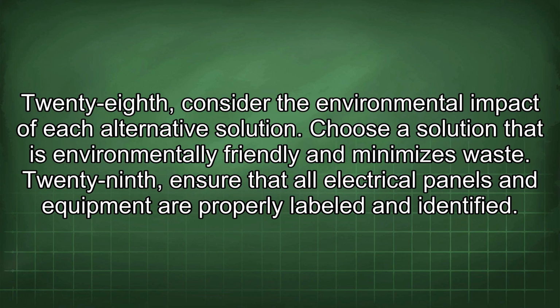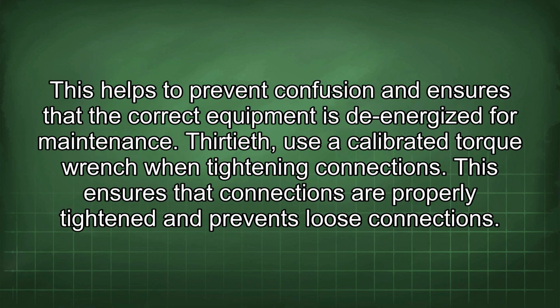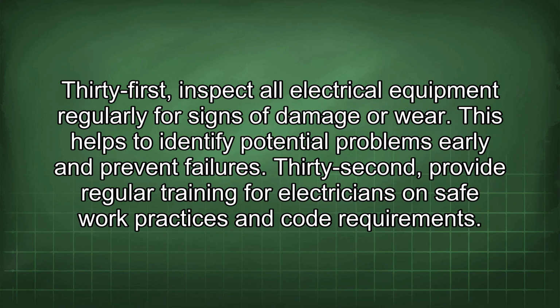29th, ensure that all electrical panels and equipment are properly labeled and identified. This helps to prevent confusion and ensures that the correct equipment is de-energized for maintenance. 30th, use a calibrated torque wrench when tightening connections. This ensures that connections are properly tightened and prevents loose connections. 31st, inspect all electrical equipment regularly for signs of damage or wear. This helps to identify potential problems early and prevent failures.